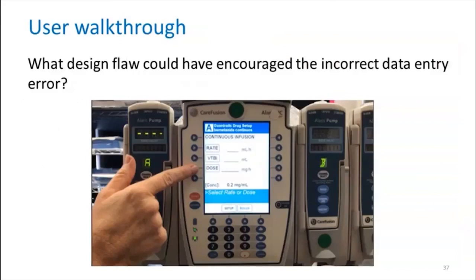So when programming an infusion pump, what the nurse first does is select the dose field using the arrow key on the right-hand side. Then the next thing they do is enter the dose values using the keypad at the bottom of the screen. Once they have entered the dose, the rate value will automatically populate.